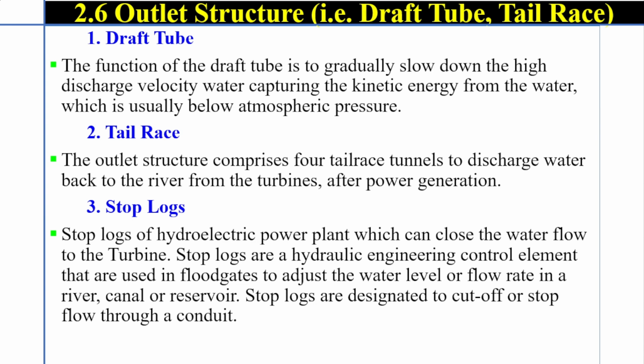Outlet structure, that means draft tube and the tail race. Draft tube. The function of a draft tube is to gradually slow down the high discharge velocity water, capturing the kinetic energy from the water, which is usually below atmospheric pressure. Terrace. The outlet structure comprises four tail race tunnels to discharge water back to the river from the turbines after power generation.